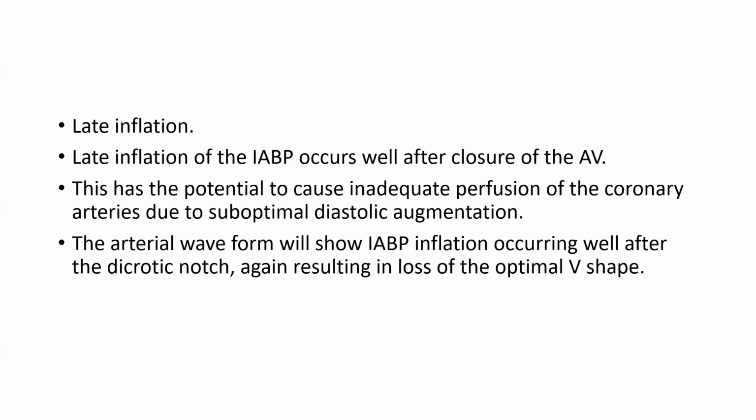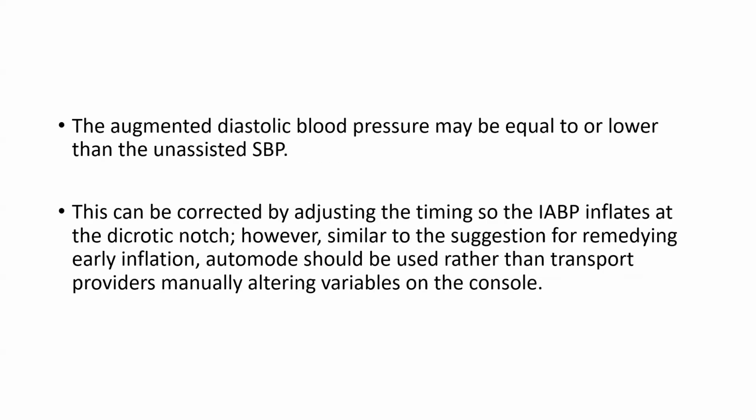Late inflation of the IABP occurs well after closure of the AV. This has the potential to cause inadequate perfusion of the coronary arteries due to suboptimal diastolic augmentation. The arterial waveform will show IABP inflation occurring well after the dicrotic notch, again resulting in the loss of the optimal V shape. The augmented diastolic blood pressure may be equal to or lower than the unassisted SBP.